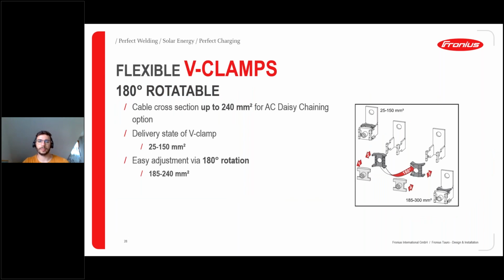Yeah, we always talked about the V-clamps already. The V-clamps look like this, and they have a little bit of a cool feature. You can flip the V-clamp and rotate it, and then you have different sizes or different cross sections of cable possible to connect to it. So in the one place of the V-clamp, you can clamp 25 to 150, and then you turn it around 180 degrees and you have a bigger V-clamp available, which you can use for 185 to 240 square millimeters. So really nice feature here and very easy and fast to do as well.